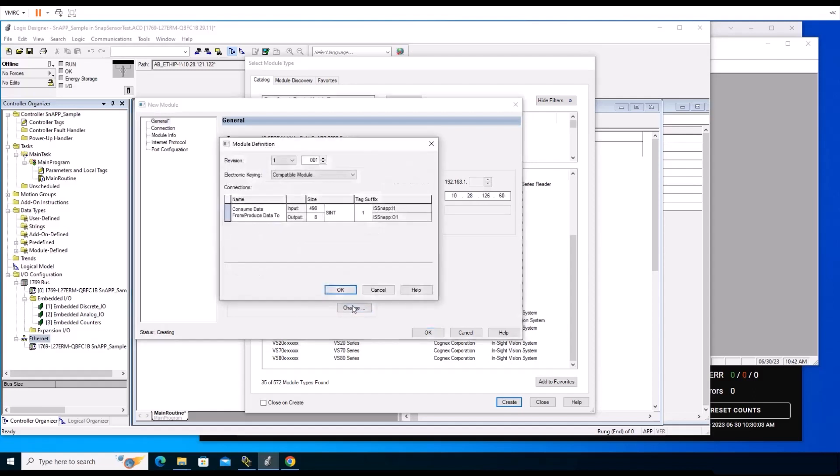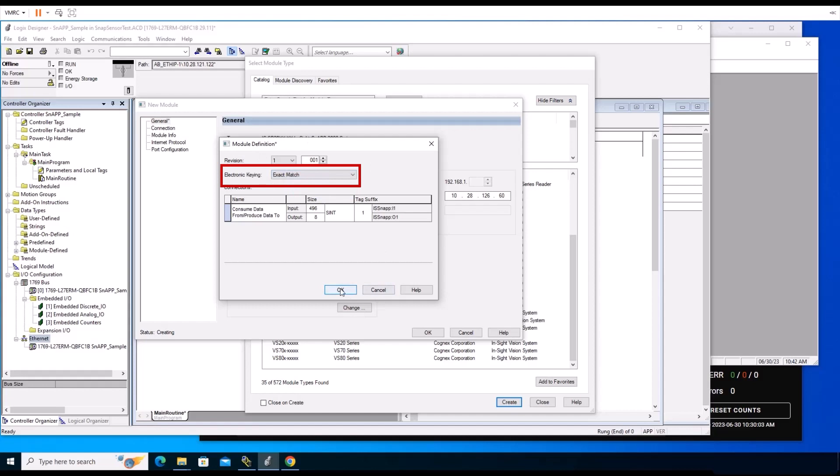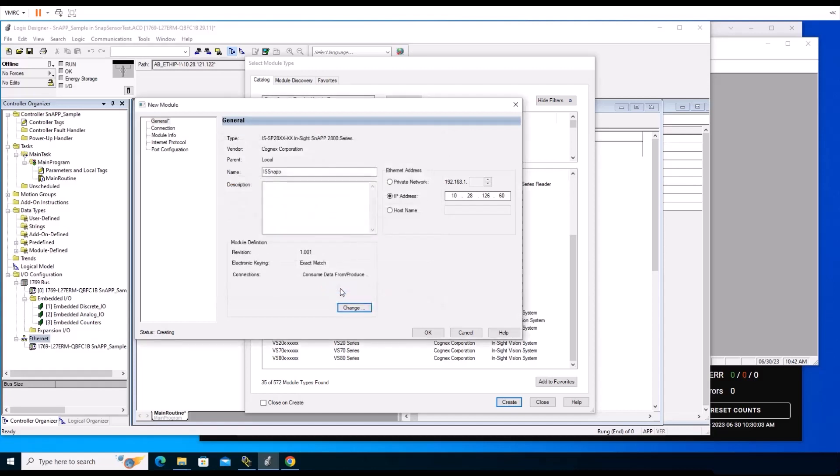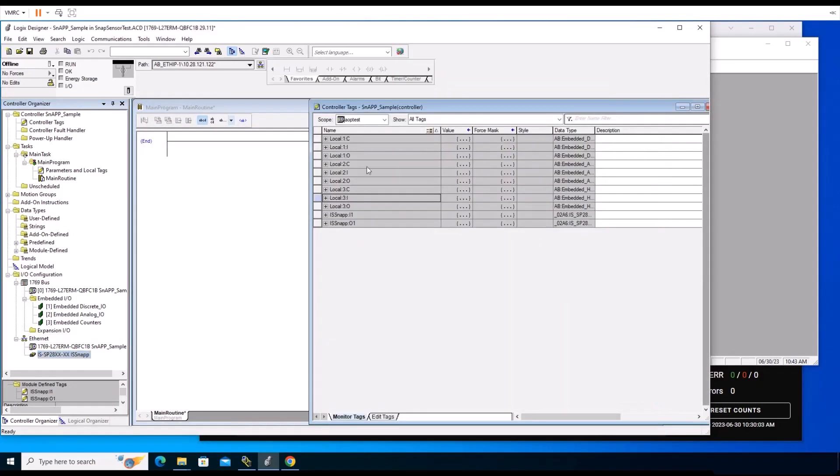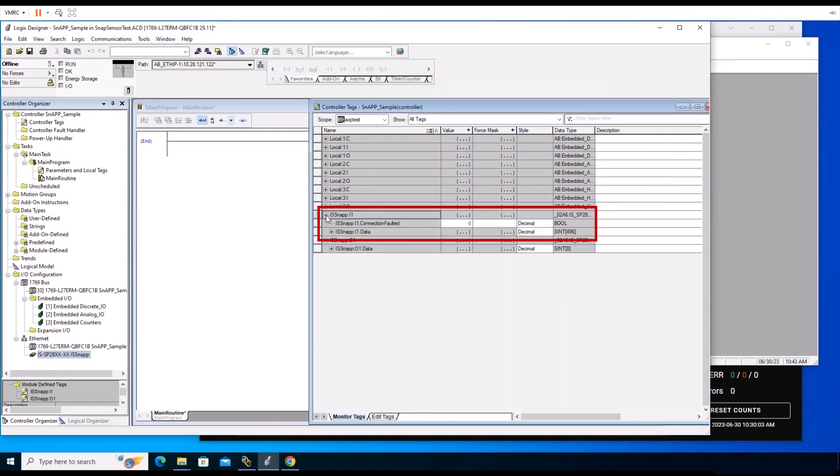You also have the option to change your keying under the Module Definition section. Change electronic keying to Exact Match from the drop-down list and click OK to finish. Return to the Logix Designer screen. You will notice under the Controller Tags section that there are two new sets of tags created from the EDS files for the In-Sight SnAPP.